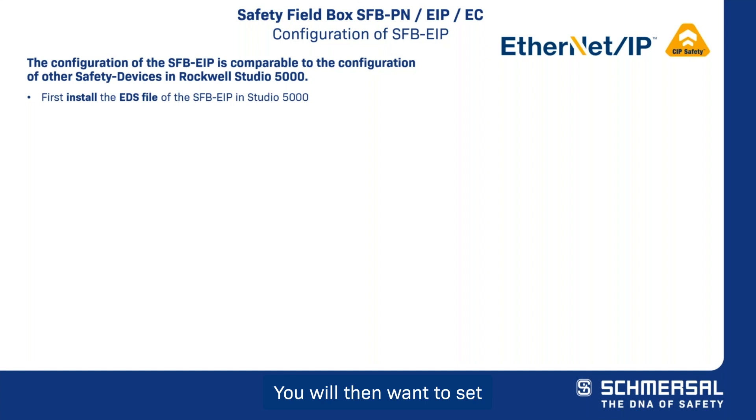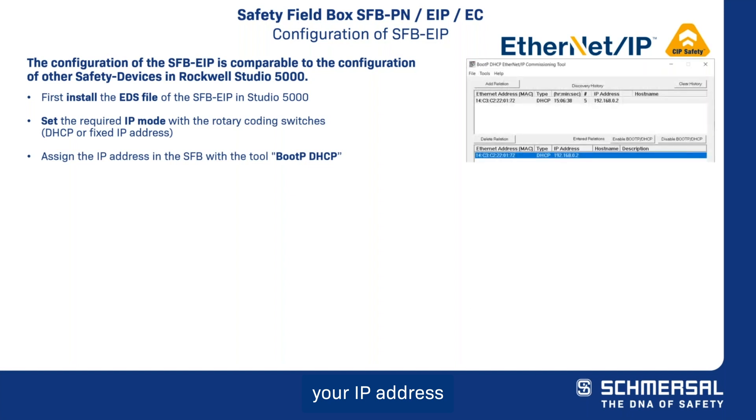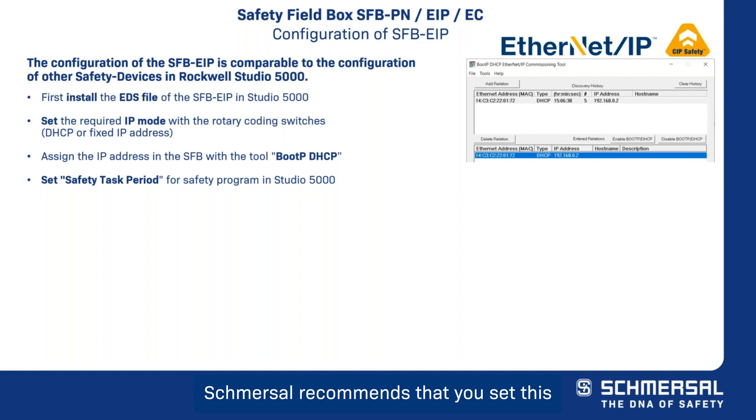You will then want to set the safety field box for either DHCP or fixed IP addressing. Next, assign your IP address in the safety field box with the BootP DHCP tool. Then, set the safety task period in Studio 5000 — Schmersal recommends setting this to 20 milliseconds.